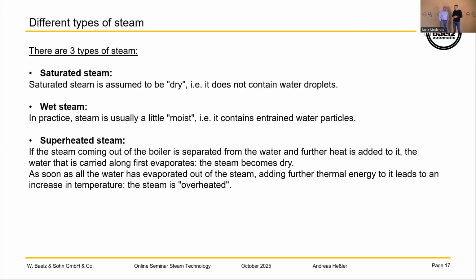For heat transfer applications, normally you need saturated steam temperature, because that is where the steam gives more energy to the phase change. When you have superheated steam, say 10 degrees superheated, you first need a lot of area to cool down the steam to saturated steam temperature, so you want to have nearly saturated steam. So again, the most energy is transferred by the change of steam into water, condensing, and in the other direction, the most energy you have to put in is from getting water to steam. All right, Andreas. Thank you. Welcome.